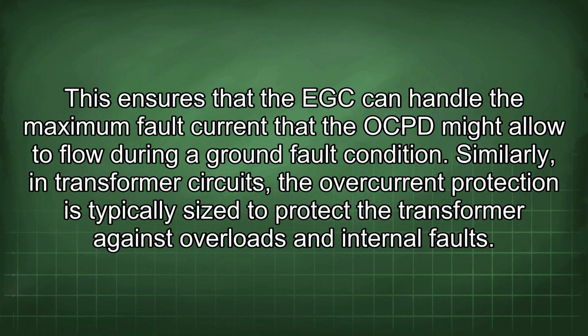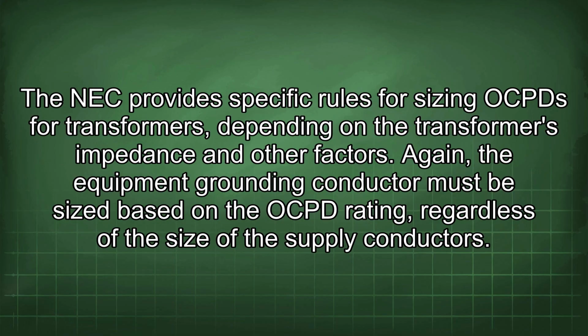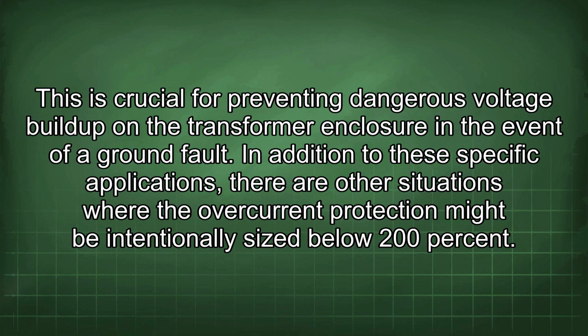Similarly, in transformer circuits, the overcurrent protection is typically sized to protect the transformer against overloads and internal faults. The NEC provides specific rules for sizing OCPDs for transformers, depending on the transformer's impedance and other factors. Again, the equipment grounding conductor must be sized based on the OCPD rating regardless of the size of the supply conductors. This is crucial for preventing dangerous voltage buildup on the transformer enclosure in the event of a ground fault.